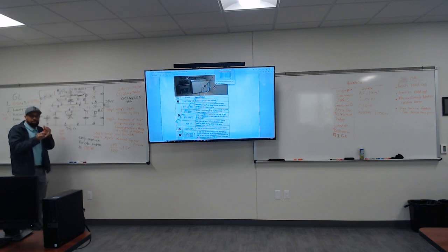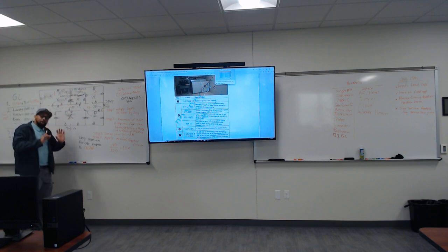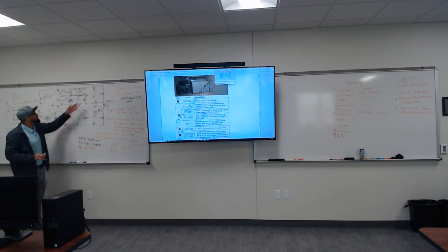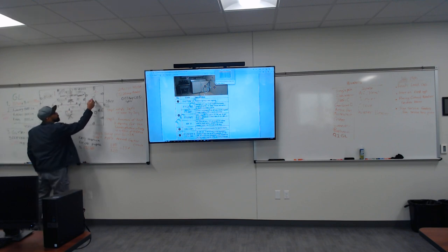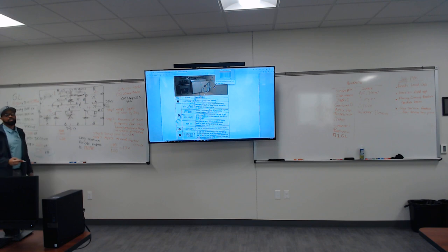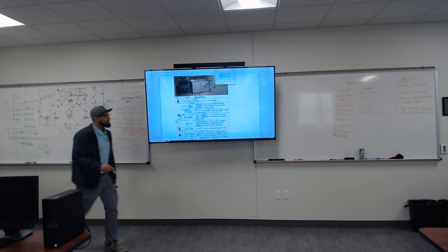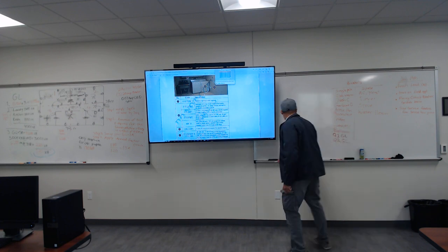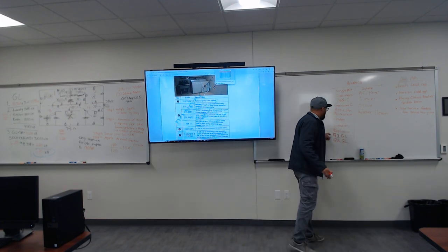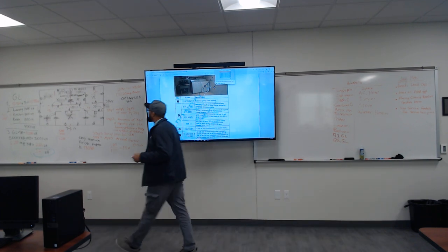Because in the article that y'all have, it said only plugs for a laundry can be on a dedicated laundry circuit. The light's going to have to be somewhere else, probably with the rest of the stuff, but it's still on quadrant two. Let's account for quadrant two. We got one, two lights, three, four, five, six. I don't even have to do any calculation. Let me just put quadrant two for its own. That's two, so I got 14 left, so we're good.